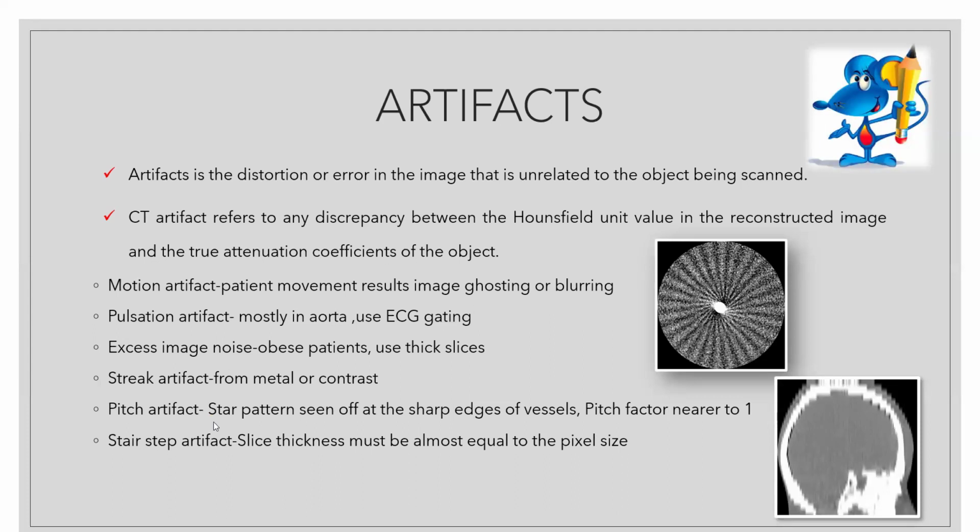Coming to pitch artifact, this is the star pattern seen at the sharp edges of the vessels. The pitch factor should be kept nearer to 1. And another is stair step artifact. Slice thickness must be almost equal to pixel size to eradicate this stair step artifact.